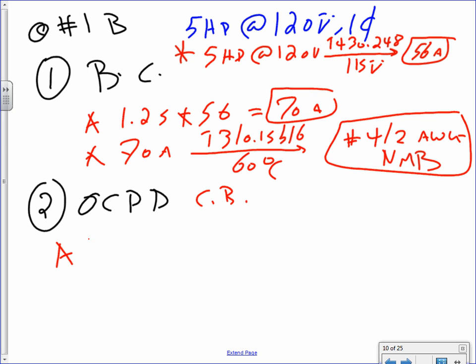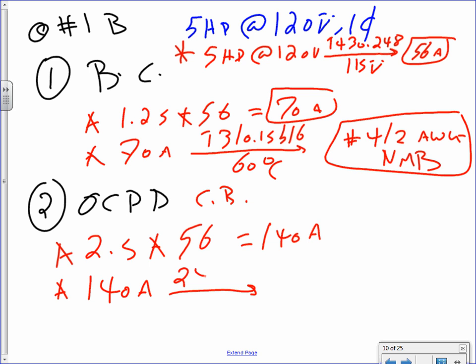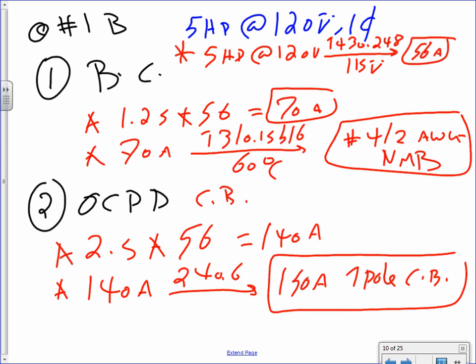Circuit breaker, the same thing. You take the 2.5, multiply it by 70. Not the 70, sorry, the 56. 56. That will get you 140 amp. And then you take 140 amp, take it to 240.6, and that'll get you 150 amp. Single pole. I don't know if they even do that circuit breaker. So I'm not sure if they even do that 150 amp single pole. I doubt that they will do it, but does that make sense? Again, put a question mark if it's doable. 150 amp circuit breaker. That's number two.